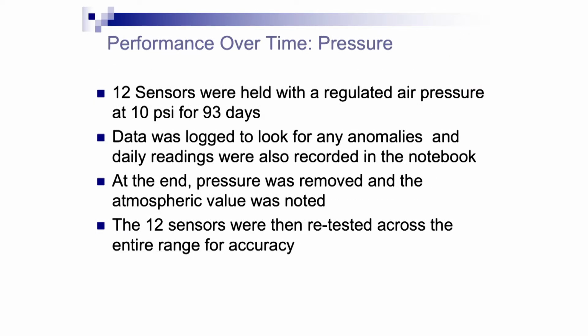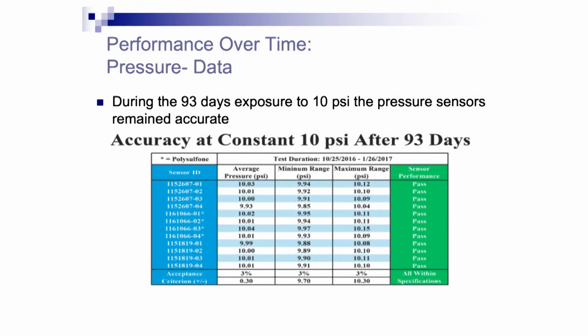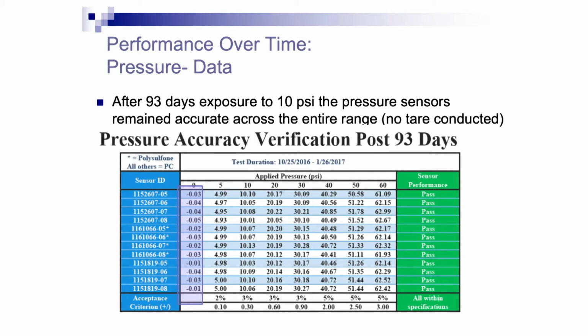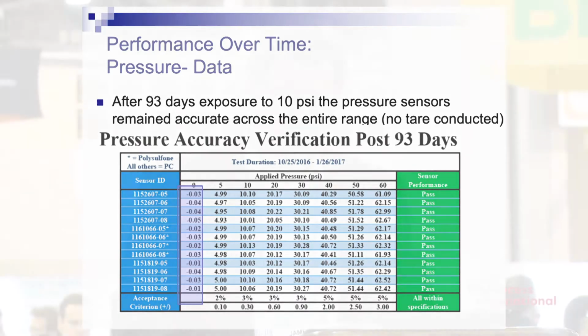So we held 12 sensors with air pressure for 93 days. We looked at the data periodically and recorded it. At the end, the pressure was removed, and we were particularly interested in whether they went back to zero after that extensive period of time. So this was the min and max pressure that was recorded over the 93 days. They were all maintained with pressure around 10 psi. And this is the data after the 93 days. The important data is shaded in the first column on the left. You'll see they all pretty much went back to zero after 93 days, which is very important. And when tested with the calibrated gauge, they were all within specification. So there was no drift of zero and no drift in accuracy.